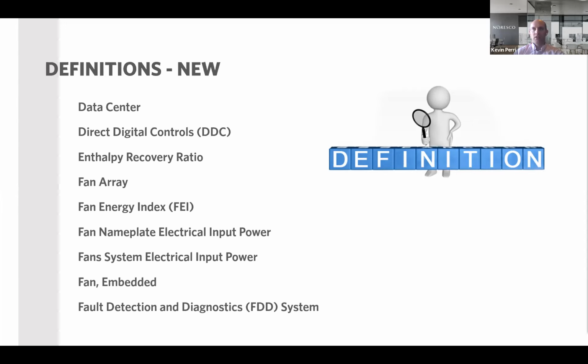So for example, data center systems is defined as HVAC systems and equipment or portions thereof used to provide cooling or ventilation in a data center. So that's data center systems. But they also added data center, which is a room or series of rooms that share data center systems whose primary function is to house equipment for the processing and storage of electronic data, and that has a design total ITE equipment power density exceeding 20 watts per square foot, and the equipment load greater than 10 kilowatts. So it's getting a little bit more specific.